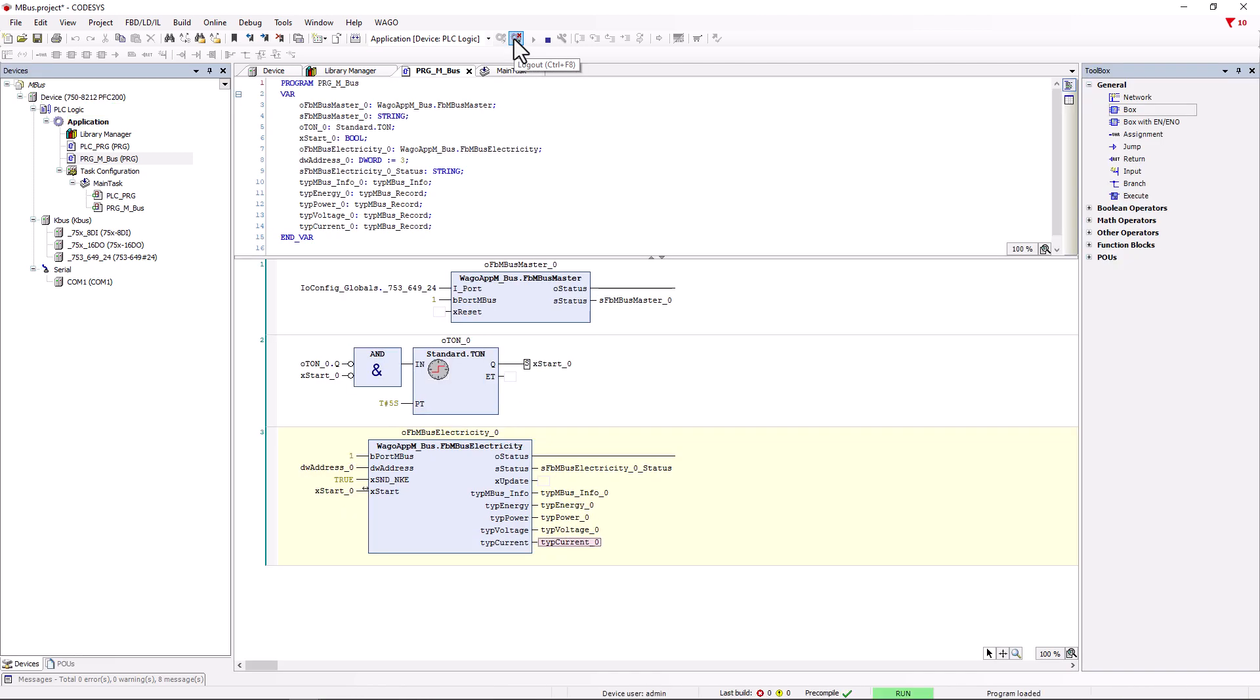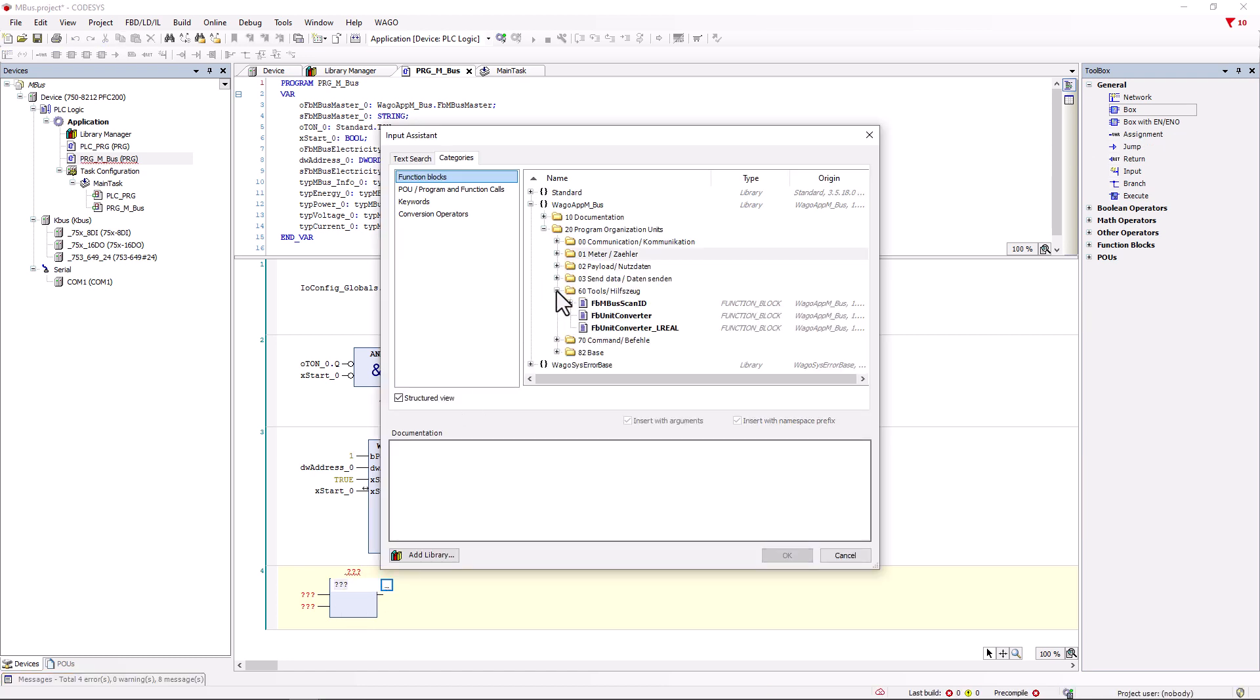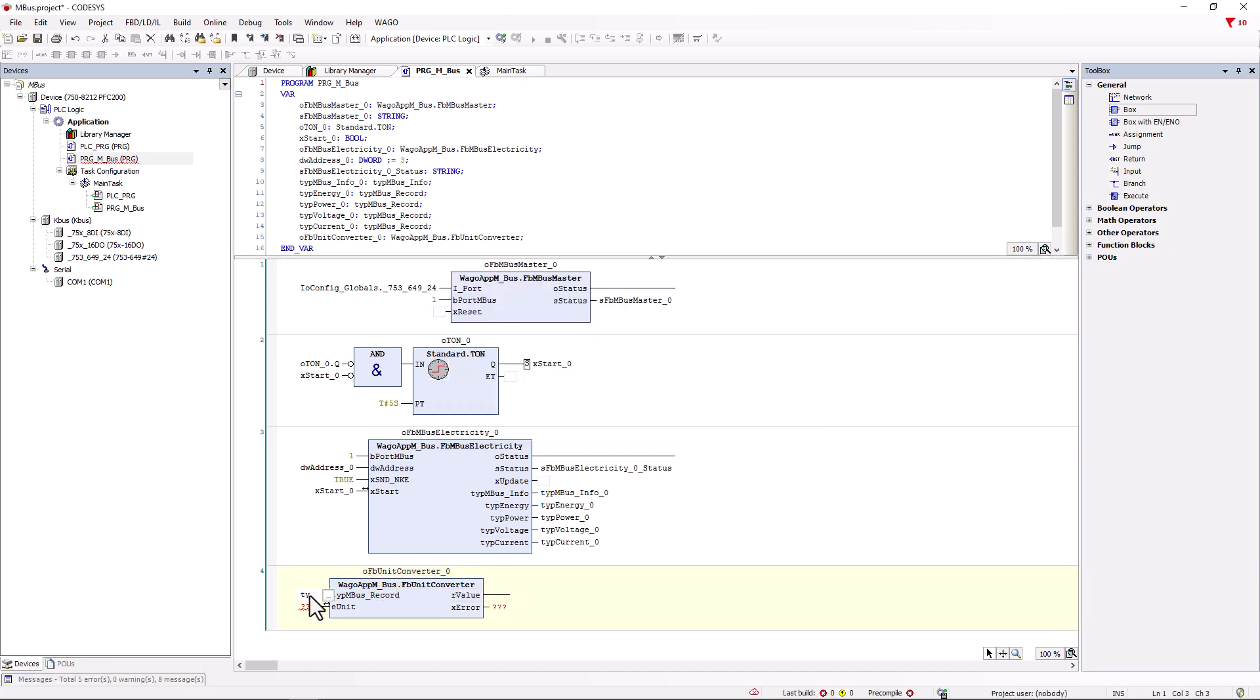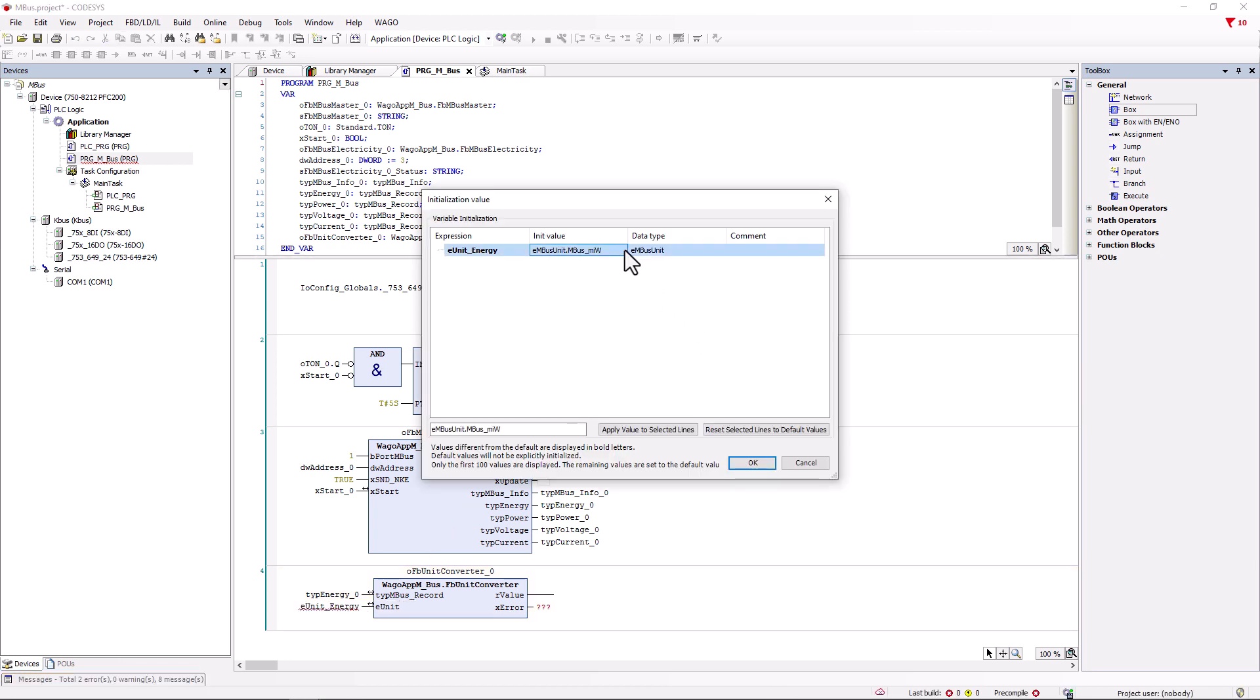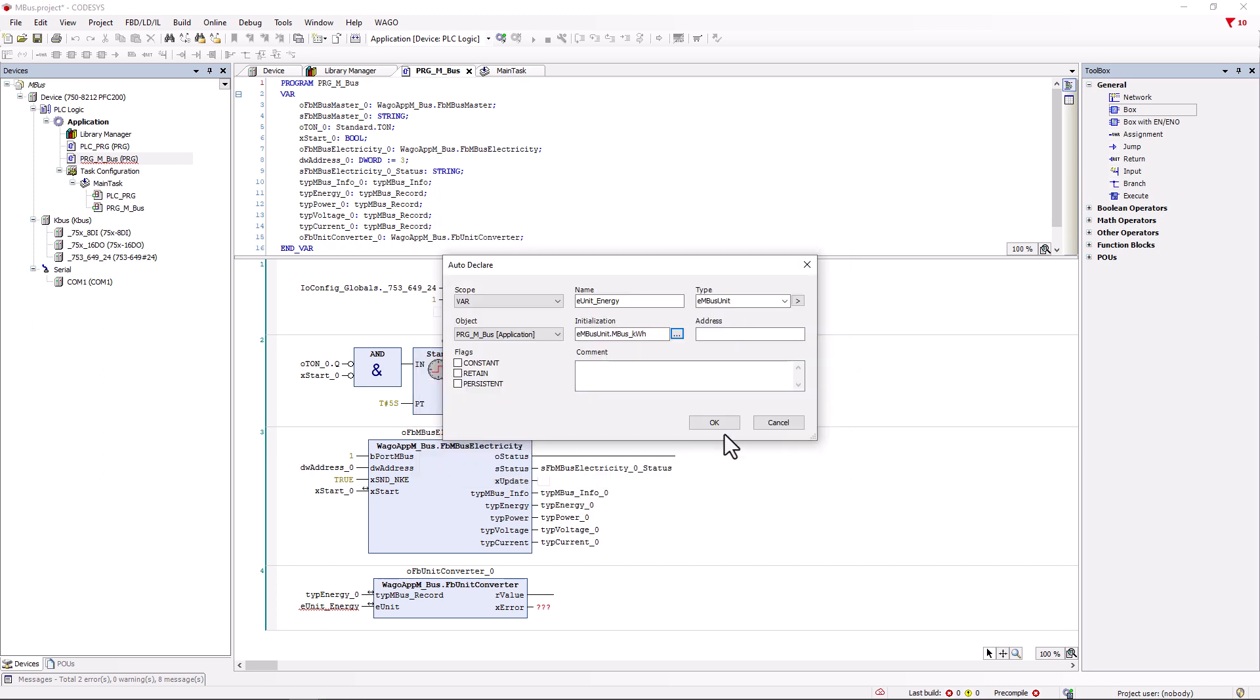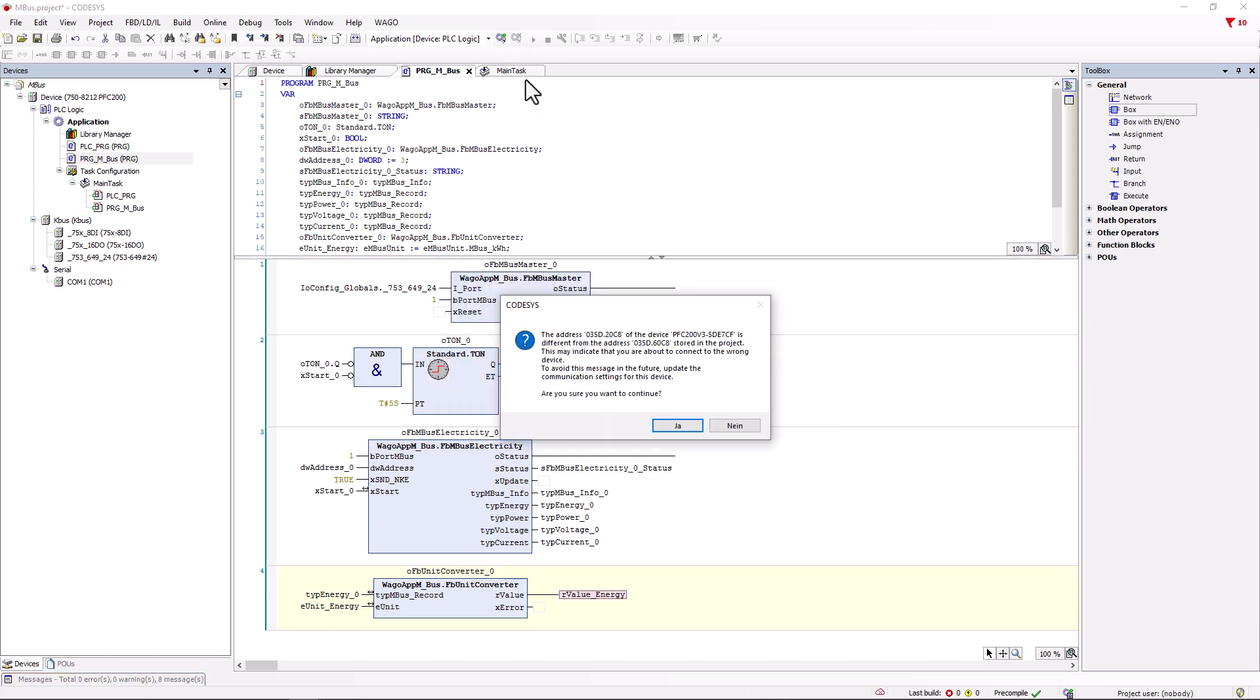To do this, we log out again and add a new network. We are now creating a new box and we can find the function block FB_unit_converter in auxiliary tools in the WAGO MBUS app. This is sufficient for most applications and the long real version of the converter is only required for very high counter values, for example in the megawatt or gigawatt range. For example, we create the type_energy_0 variable at type M-BUS record output. For input E-Unit, we assign a new variable with the name E-Unit_energy and initialize it with the unit kWh in the auto declaration via the three points in the column init value. The converted value is now at the R_value output and we assign a variable here. X_error is not required in this case. This network is ready.